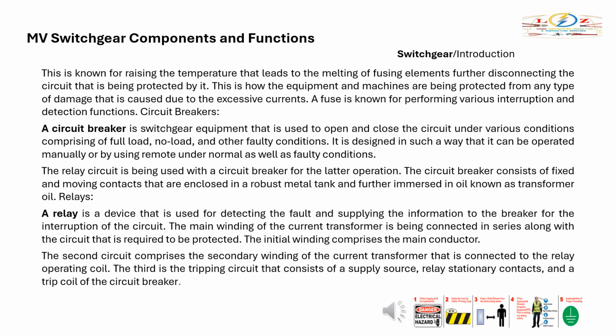Circuit breakers. A circuit breaker is switchgear equipment that is used to open and close the circuit under various conditions, comprising full load, no load, and other faulty conditions. It is designed in such a way that it can be operated manually or by remote under normal as well as faulty conditions. A relay circuit is used with a circuit breaker for the latter operation. The circuit breaker consists of fixed and moving contacts that are enclosed in a robust metal tank and immersed in oil known as transformer oil.